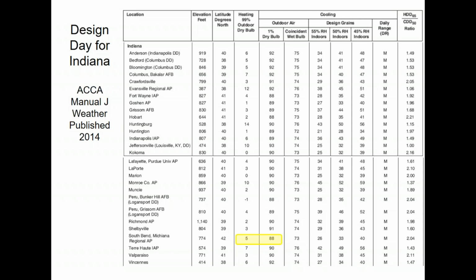So that's what we're going to design for, 5 degrees on the heating side. And up at the top of the column where it says heating 99%, that means 99% of the hours it'll be above 5 degrees in South Bend, Indiana. Only 1% of the time will it ever be below 5 degrees on a 30-year rolling average.